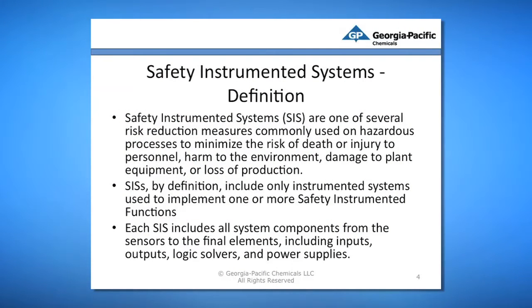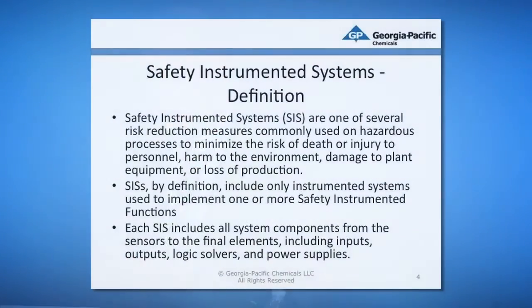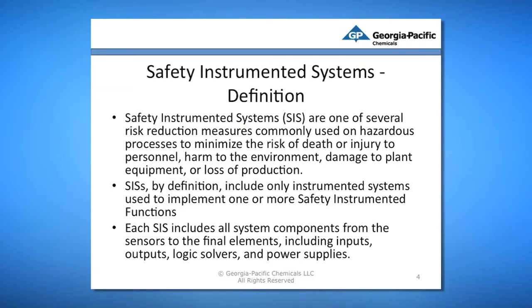A little safety instrument system definition here. SIS, safety instrument systems, are one of several risk reduction measures that are commonly used on hazardous processes to minimize the risk of death or injury to personnel, harm to the environment, damage to the plant equipment, or loss of production. Some examples of other risk reduction measures are process design, of course, relief valves, rupture discs, human intervention, fire protection systems, and so on. The SISs are never used as the only risk reduction measure and are usually used only as the last resort if other available risk reduction measures are not sufficient to reduce the risk to the acceptable levels.